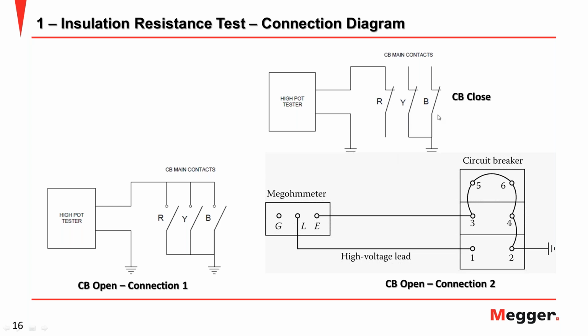You short red and blue to the ground. If you test phase blue, you need to short red and yellow to the ground. So this is the wiring connection for when the CB is closed. When the CB is open, you can follow like this. You can test each pole, red, yellow, blue, in the phase part and the return part. Where is the return part? You need to connect it to the ground. So this is the wiring connection of the insulation resistance test of the breaker.